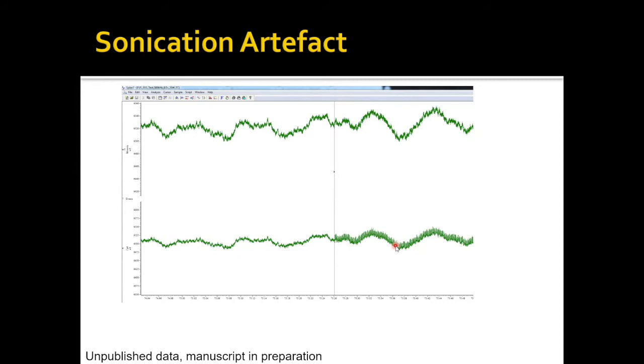We found an easy way to get rid of that is to filter the signal. It turns out that the artifact is mainly related to the pulse repetition frequency, which in this case is set to 1,000 hertz. With a low pass filter, you can pretty much remove this artifact fairly easily, which is good.